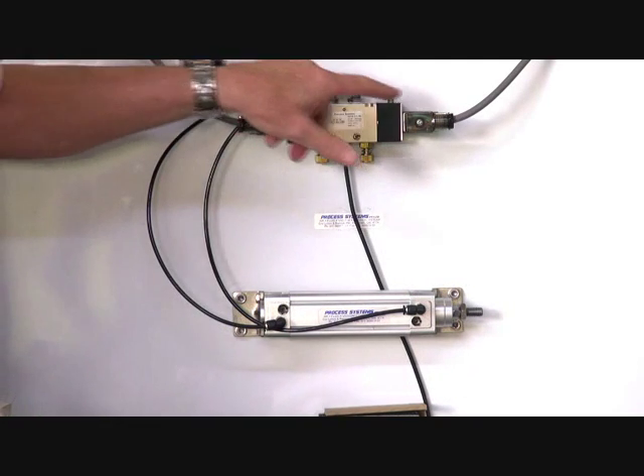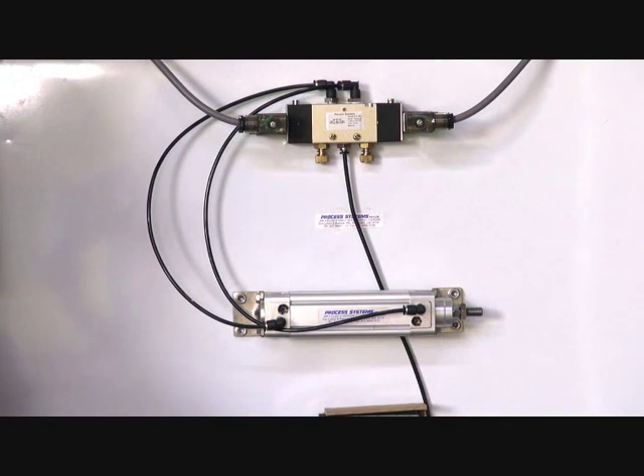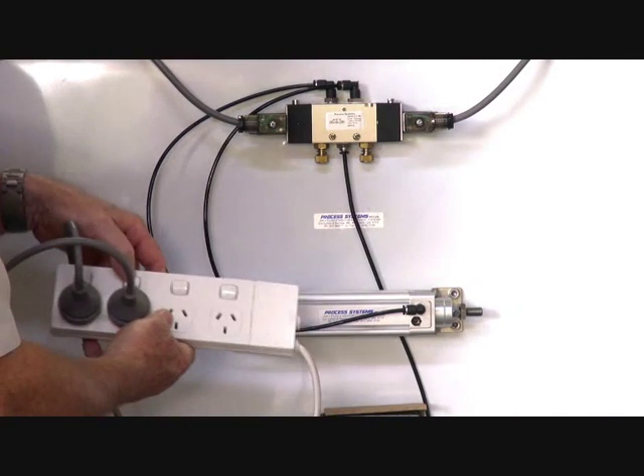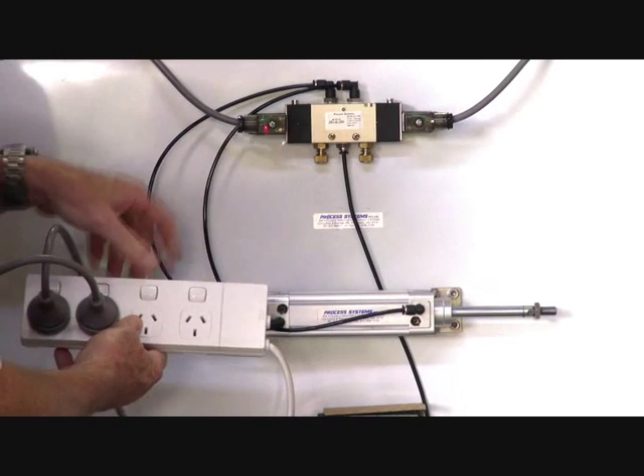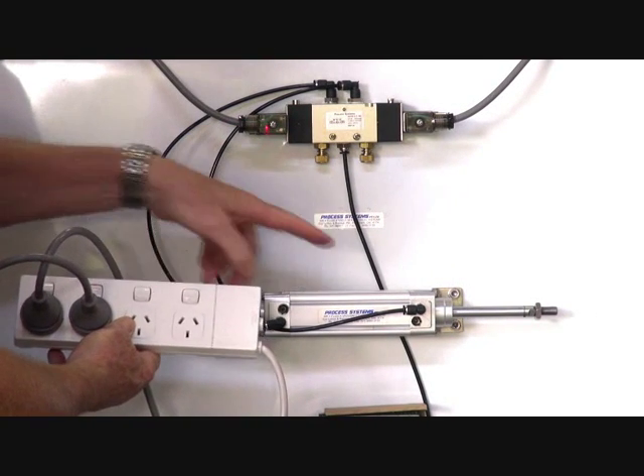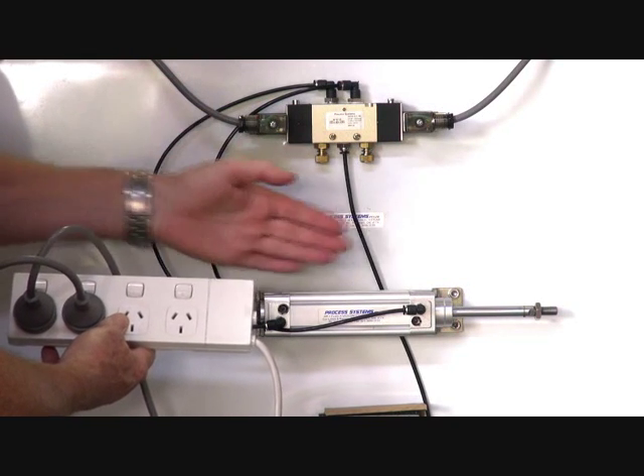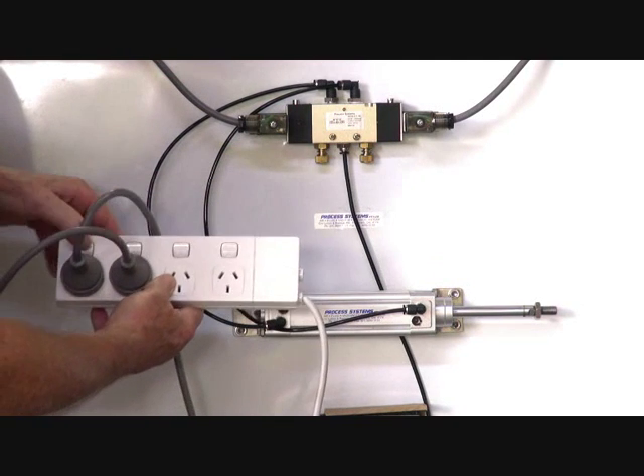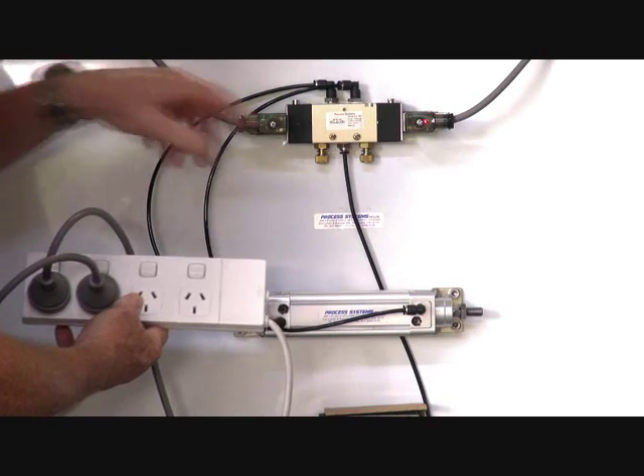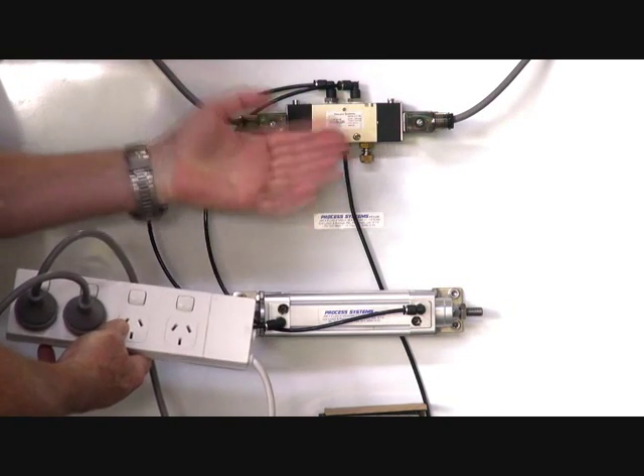The valve has electrical LEDs in the top here. If I turn the power on, you'll see the LED comes on this end, unit goes out. Turn the power off, it stays there. Power's removed, unit is still in that position. Turn the power on the other end, LED comes on, switches back. Turn the power off, it stays there. It's stable in both functions.